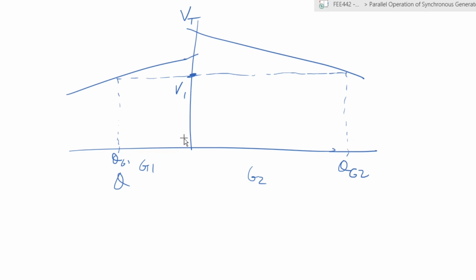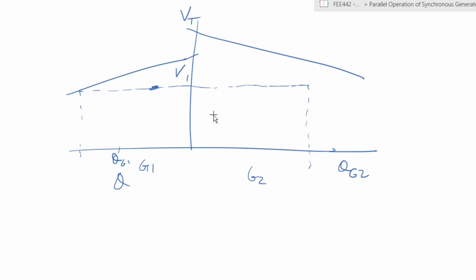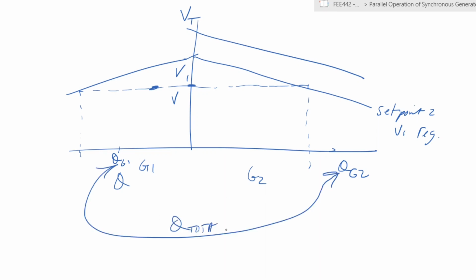If we were to change the values of those, and we shift it along, say, up to down here, that would mean that you now have a second value of voltage, V2, and you then need to have set point 2 for your voltage regulator. And that matches the two of them. So you have QG2 and QG1 being the total reactive power that you're supplying to this system.